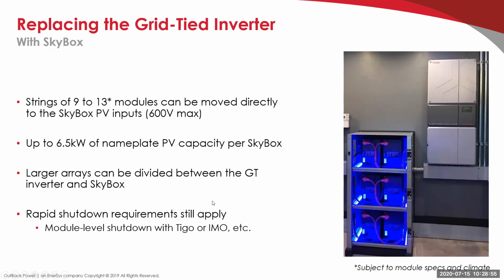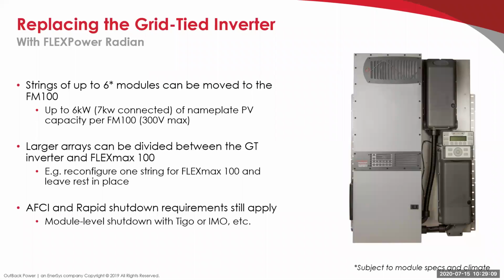Although you might want to check with your local authority having jurisdiction and find out whether or not they would make you come up to the latest code cycle. You can also do this with the Radian, but as Chris mentioned earlier, these are 300 volt charge controllers. So you might have to take that 600 volt string and cut it in half and put half of it to one charge controller and half to the other. So it gets a little bit more complicated with the Radian.